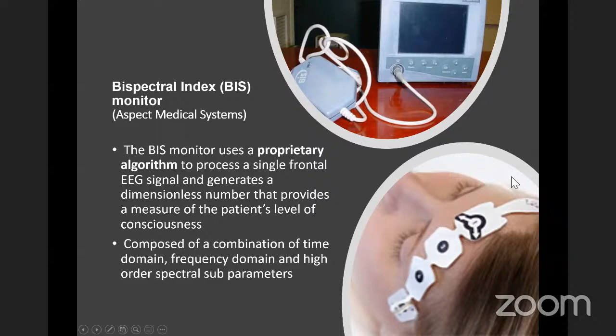So how to apply the electrode? This is another important thing to know, because this is what determines the quality of the signal. First of all, the first important thing is to wipe the forehead where you are going to apply the electrode. Wipe it clean with spirit alcohol, and then let it dry before applying this electrode.